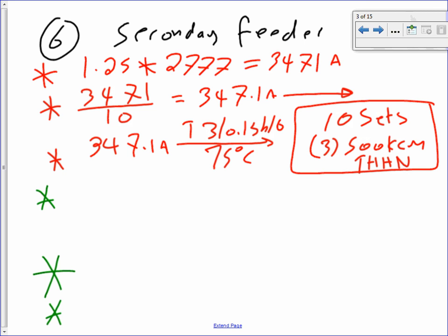Okay. Do I have a neutral on the secondary? There were 4 wires, right? We have a neutral. So let's go size a neutral. These are just for the 3 phases. Why would I always use 500? Adam, you asked me which conductor we should size.